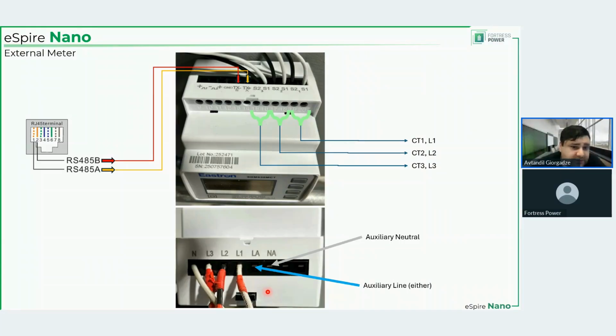That line reference cable. Let's say you have a 3-port Wago. One port will be the L1 cable, for example, that you brought from wherever you're taking the reference, let's say the main panel board, and you brought 1 wire for L1 connected to the 3-port Wago, to port number 1. Port number 2 will connect to line auxiliary, and port 3 will connect to line 1. So that way you have reference and you are delivering power.